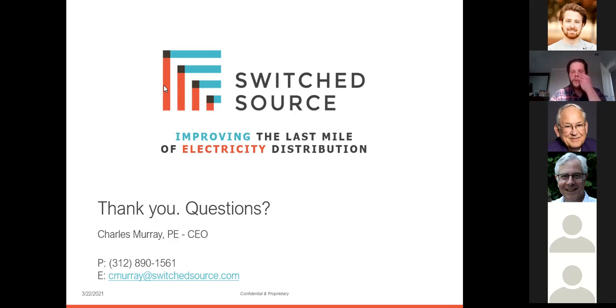Yeah, absolutely. We fall into three categories of use cases. One is what we'd call upgrade deferrals, now rebranded as non-wires alternatives. If parts of your system are being overloaded, can you use this device as a tool so you don't get thermal overload? It's usually on a substation or distribution circuit, so you're getting real power set points to balance power during key parts of the day to other infrastructure. This couldn't necessarily be done with a simple switching procedure, or you might have different voltages around a substation so you can't shed load to those circuits.